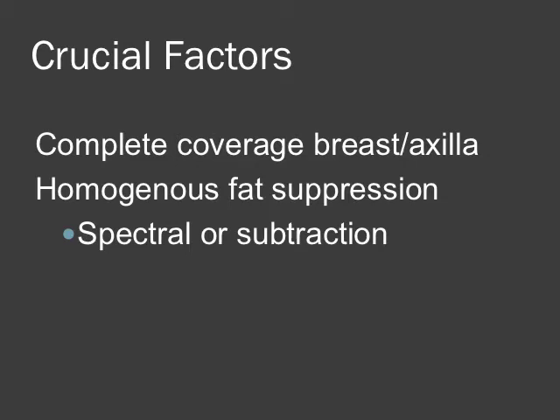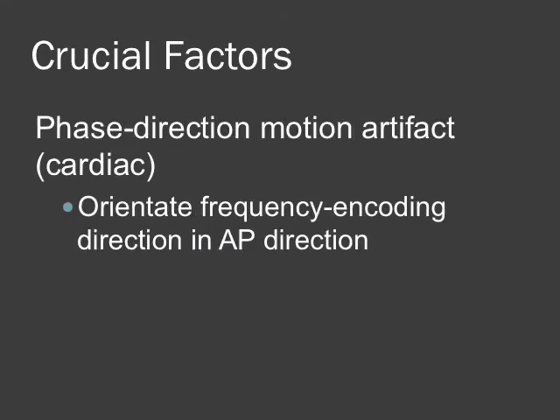You must be able to cover the complete breast and axilla, and this requires some training on the part of the technologists. MR technologists are not used to positioning breasts the same way as mammography techs, so we get mammography techs to train the MR techs to ensure all of the breast is seen up into the axilla — which is sometimes a challenge with larger breasts. Fat suppression should be very homogeneous, otherwise it's difficult to see areas of contrast enhancement. Pulsations of the heart produce a motion artifact in the phase direction, so we orient our frequency-encoding direction in the AP direction so that motion artifact goes side to side in the chest rather than through the breasts.